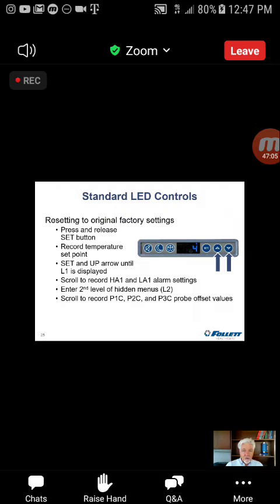So we want to go and find out what these are. So we want to scroll on a refrigerator to P1C. That's probe 1 calibrate. Hit the set button. It will show you if any offset has occurred. If it's not 0, the value should be recorded. Then we hit set to back out.